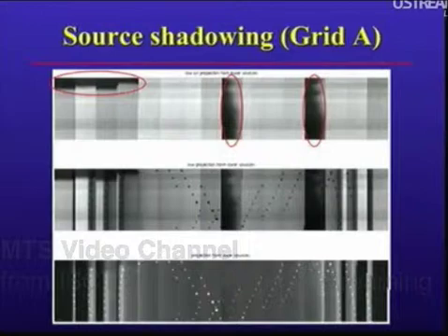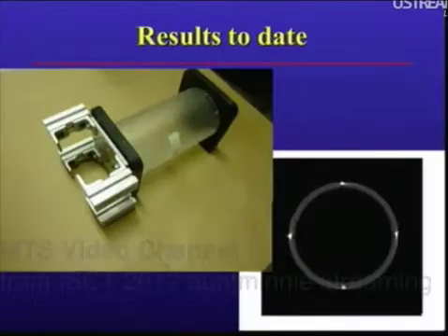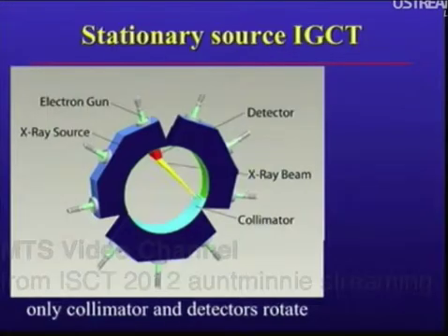The other row also had shadowing problems in different places. We were able to rescue enough of the data to actually image the BB phantom, and you see there one of the stack of slices through 4 of the BBs and the phantom. We will continue to work with this. The source is currently being repaired to correct the problem with the shadowing.